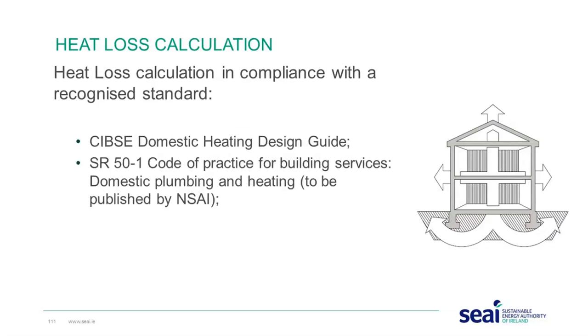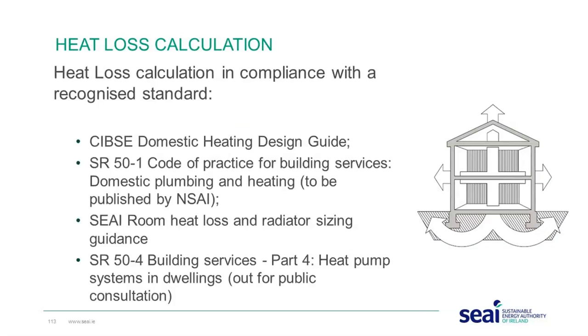Firstly, it must be done in accordance with a recognised standard. An example of some of these recognised standards are the CIBSE Domestic Heating Design Guide, SR 50-1, which is the Code of Practice for Plumbing and Heating. SEAI have guidance on it, and I'll go through that later. And finally, as Michael had mentioned, SR 50-4, which is the Code of Practice for Heat Pump Systems in dwellings. That's out for public consultation, and I would encourage everyone here to have their say on it, to download it and make comments on it.